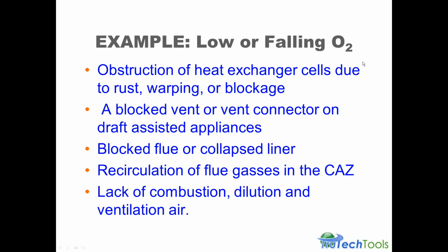We wanted to talk about some of the interrelationships and how to interpret some of the results. We do have a higher level course under development to give more technician level diagnostic and troubleshooting advice. But things like a low or falling O2 might be due to heat exchanger cell blockage, a blocked vent or collapsed liner, or perhaps even recirculation in the combustion air zone, or lack of combustion, dilution, or ventilation air. So these are some of the factors that can cause your combustion analyzer to show a low or falling O2 reading.